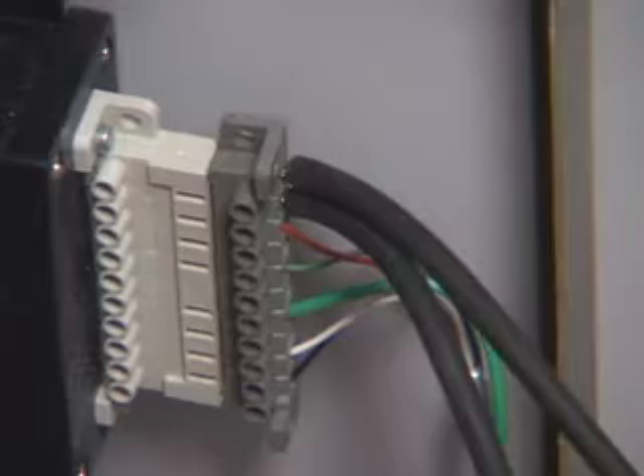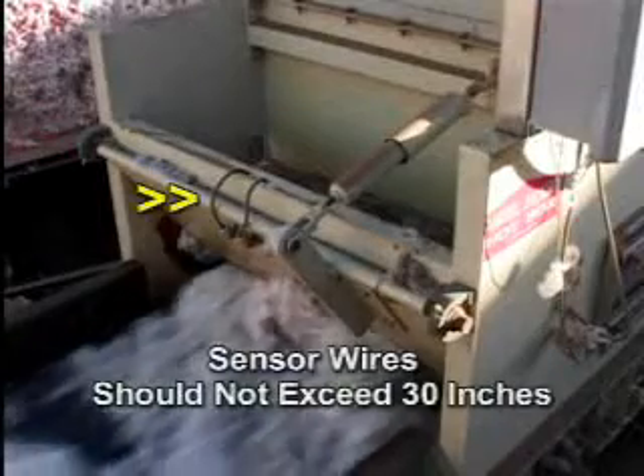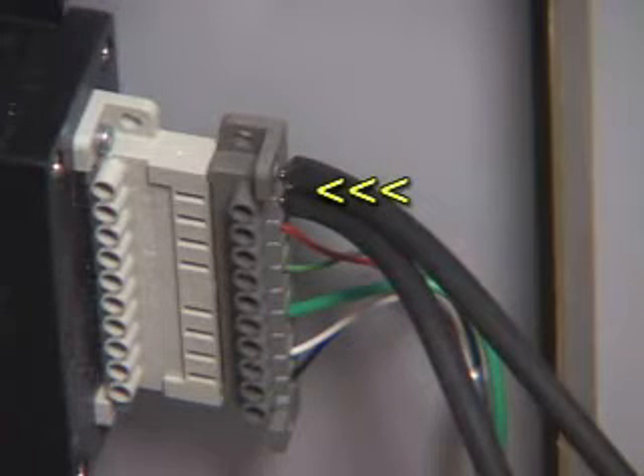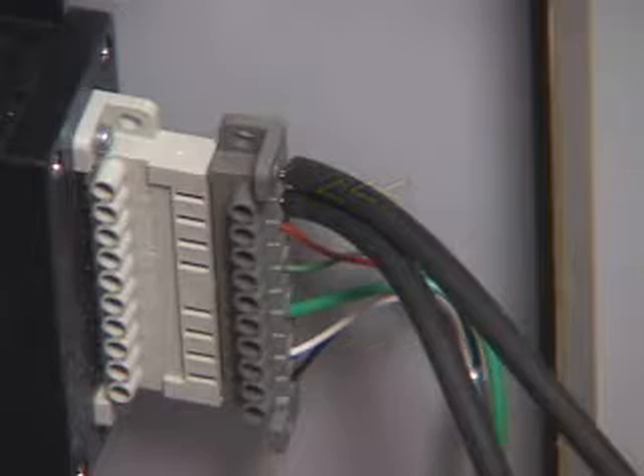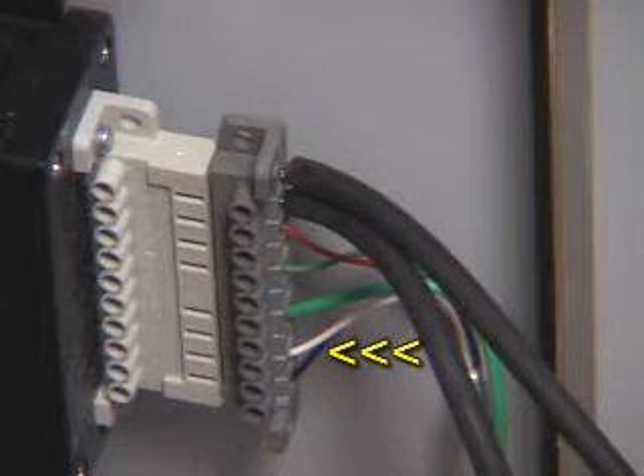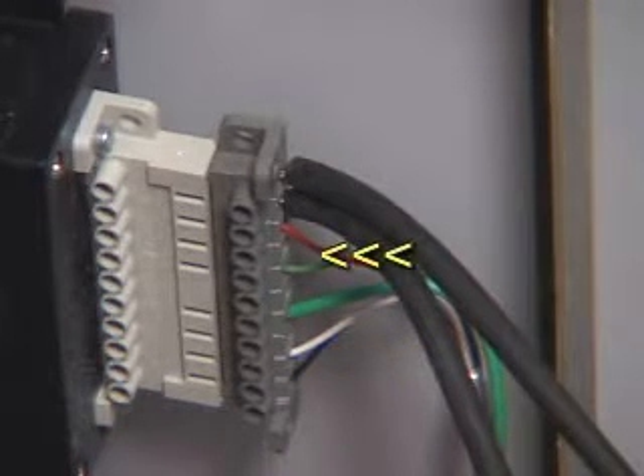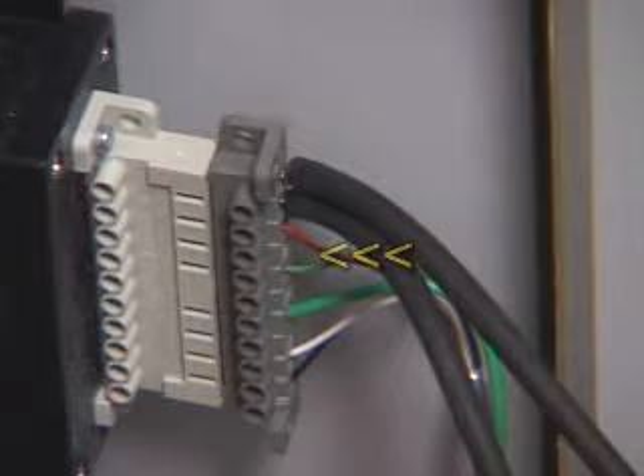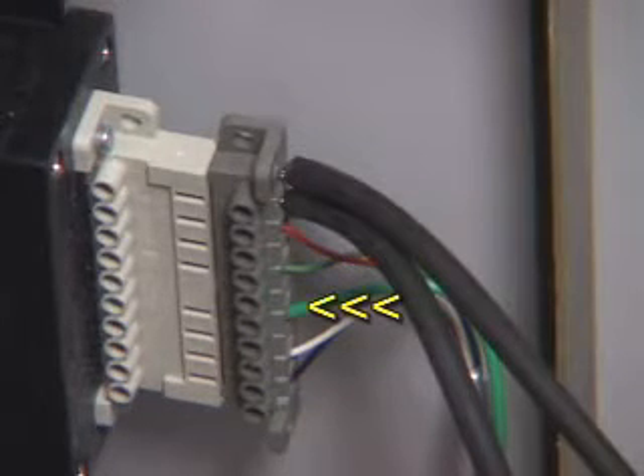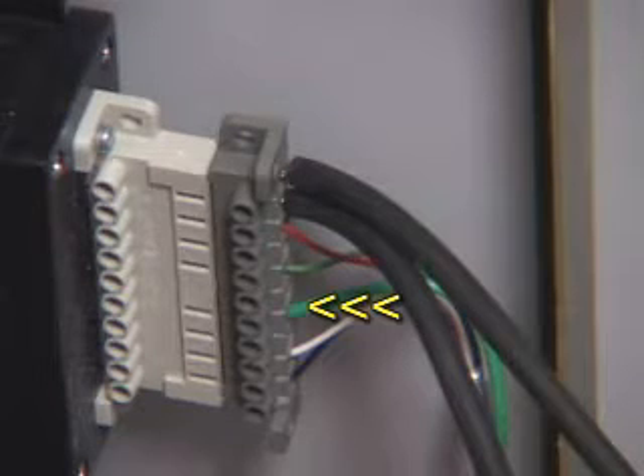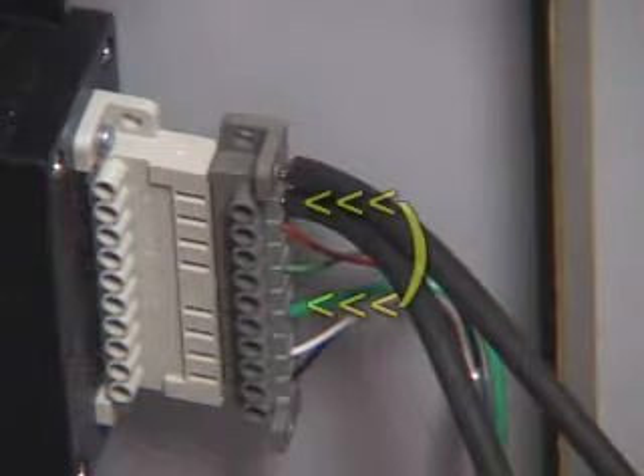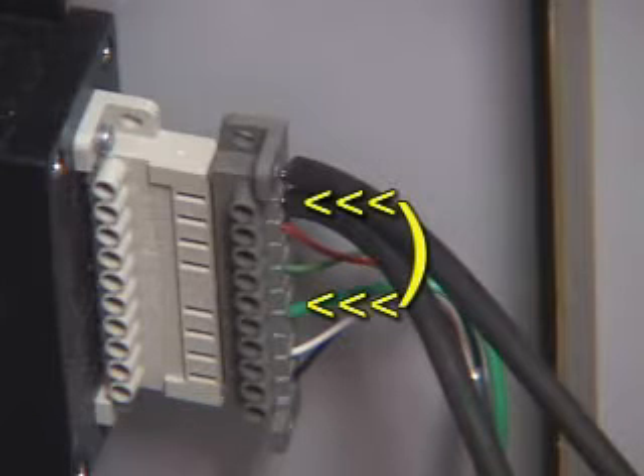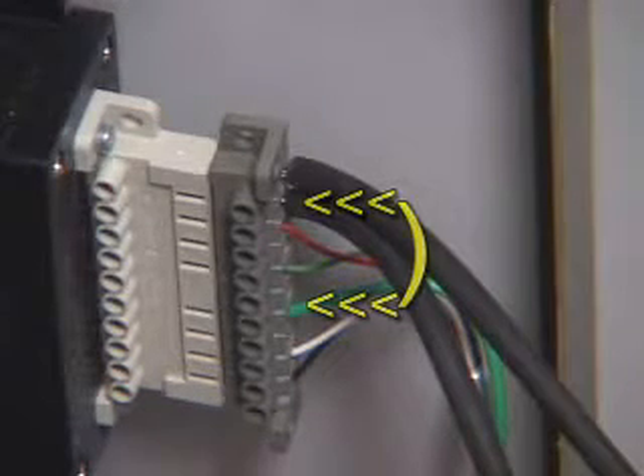On this hotbox installation, the transmitter is found in the fiberglass enclosure. 2 spark plug wires carry the resistance signal to the transmitter. These wires should never exceed about 30 inches. They connect here on terminals 1 and 2 of the transmitter. Terminals 9 and 10 on the transmitter are 24 volt DC supply. Terminals 3 and 5 are the 4 to 20 milliamp signal. Terminal 7 is ground and should be connected with a 12 gauge wire to the equipment where the sensor is mounted. Connect a short jumper between terminal 7 and terminal 2 on the transmitter for best accuracy.